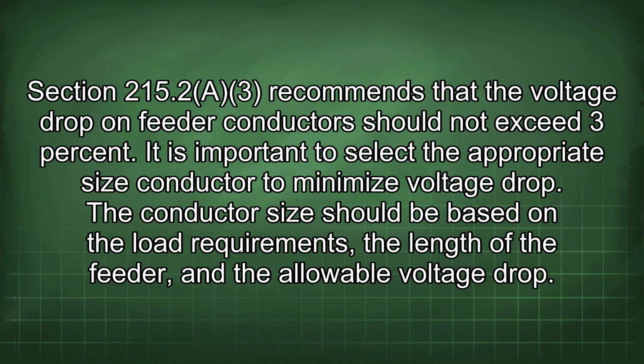Section 215.2A3 recommends that the voltage drop on feeder conductors should not exceed 3%. It is important to select the appropriate size conductor to minimize voltage drop. The conductor size should be based on the load requirements, the length of the feeder, and the allowable voltage drop.